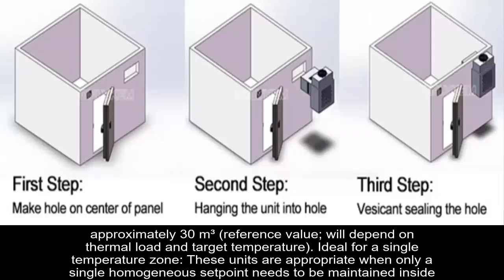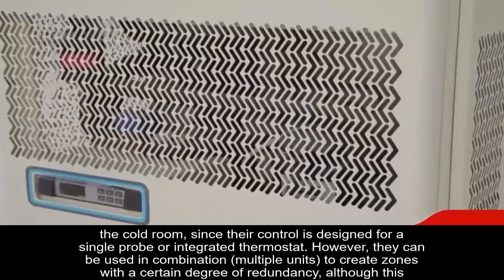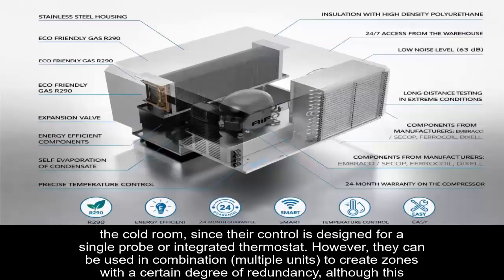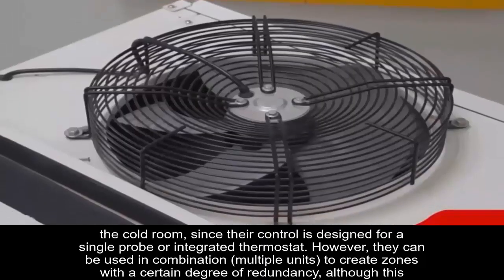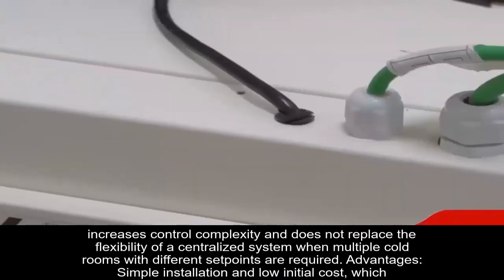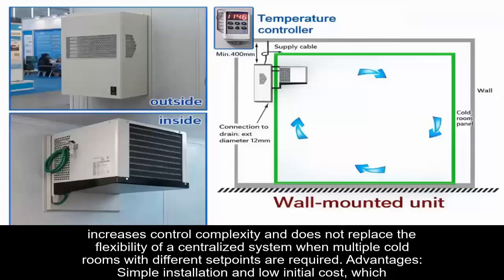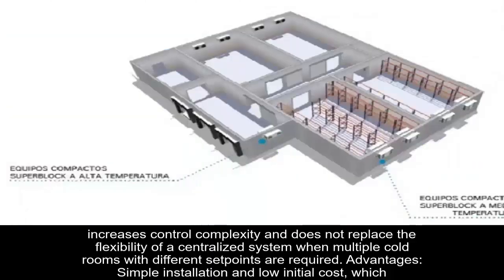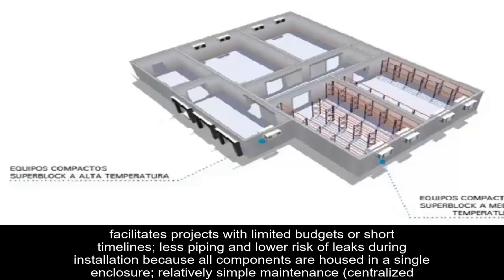These units are appropriate when only a single homogeneous set point needs to be maintained inside the cold room, since their control is designed for a single probe or integrated thermostat. However, they can be used in combination, multiple units, to create zones with a certain degree of redundancy, although this increases control complexity and does not replace the flexibility of a centralized system when multiple cold rooms with different set points are required. Advantages: simple installation and low initial cost, which facilitates projects with limited budgets or short timelines.